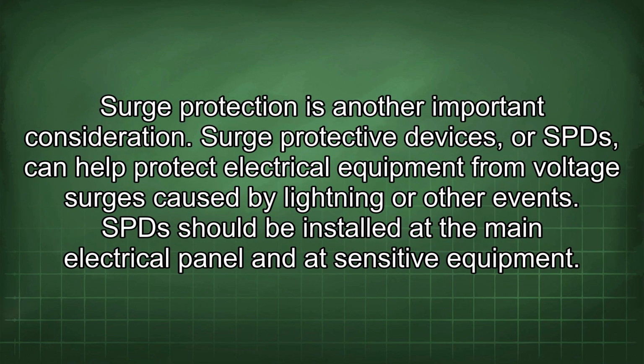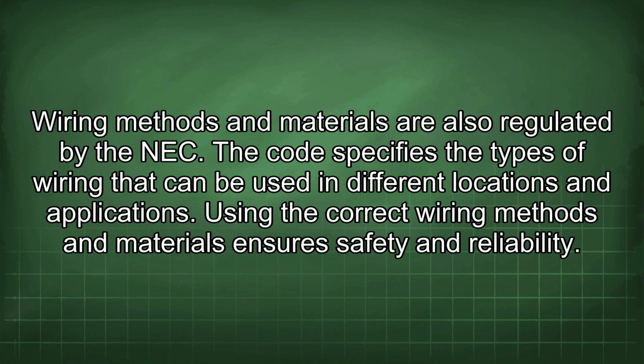Surge protection is another important consideration. Surge protective devices, or SPDs, can help protect electrical equipment from voltage surges caused by lightning or other events. SPDs should be installed at the main electrical panel and at sensitive equipment. Wiring methods and materials are also regulated by the NEC. The code specifies the types of wiring that can be used in different locations and applications. Using the correct wiring methods and materials ensures safety and reliability.